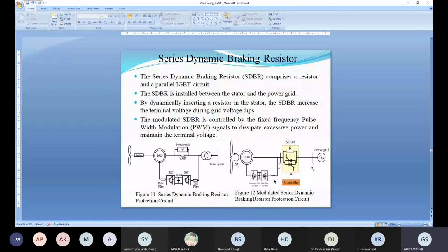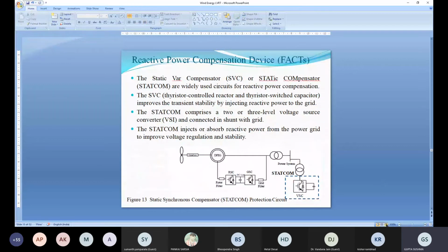Reactive power compensator circuits, all of you know, there are StatCom, DVR, SVC. These are the reactive power compensation devices. These devices are connected at the grid. They are not connected between the rotor side converter or grid side converter. These reactive power compensation devices are connected on the grid.